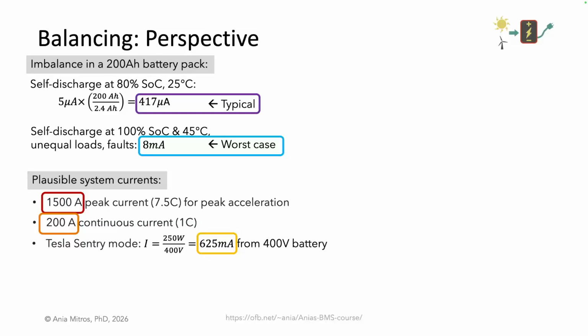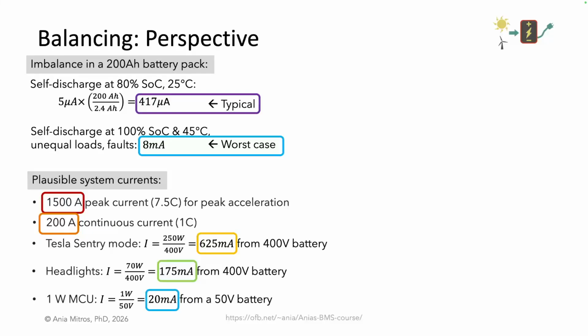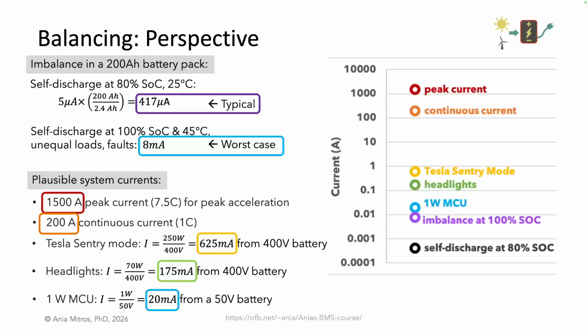Even when the application load is not present, we may have a computer or microcontroller running, or possibly other peripheral loads. Tesla Sentry Mode uses the power-hungry autopilot computer, drawing perhaps 600 milliamps from the battery. Car headlights might pull 175 milliamps at the battery. A 1-watt microcontroller monitoring a home energy storage system might pull 20 milliamps from the 50-volt battery. Imbalance is really quite small relative to these other application currents. Here, I plotted the rough numbers that we estimated on a logarithmic scale. We're looking at different orders of magnitude. As we discuss balancing, keep in mind that balancing corrects for currents that are thousands or even a million times smaller than whatever the battery is powering.